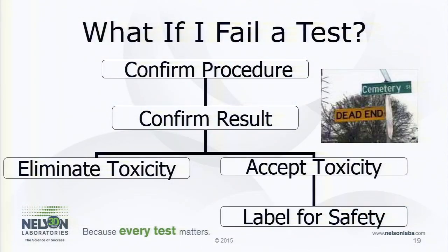Okay, the last thing we're going to cover is what happens if we fail a test. The reason I throw this in here is because this is going to happen if you do biocomp long enough. But I hate it when people freak out when they fail a test, especially cytotoxicity. I've seen people spend millions of dollars and tons of time developing a product, and they fail cytotox and they go, that's it, we're done, just throw it away. Please don't do that. A failed cyto doesn't necessarily mean the end of the world, okay?